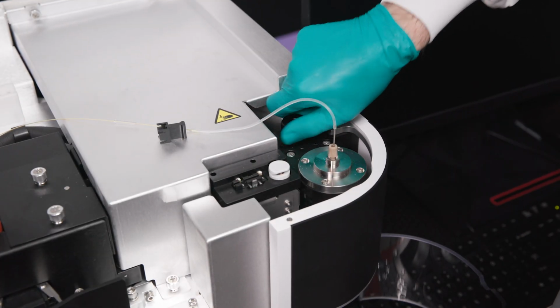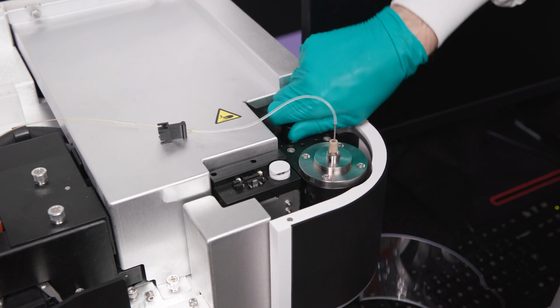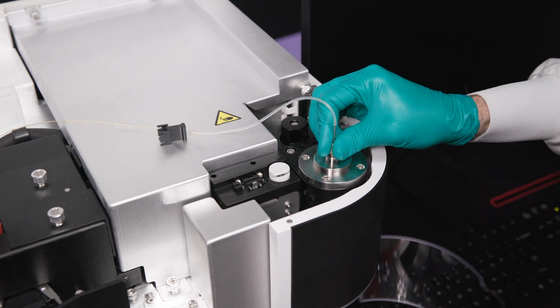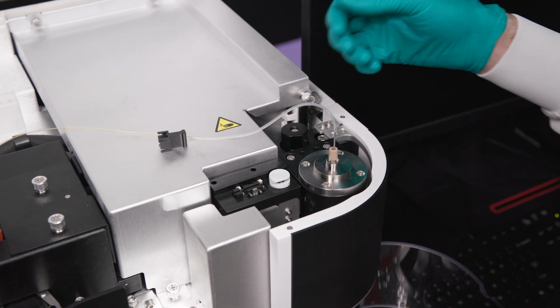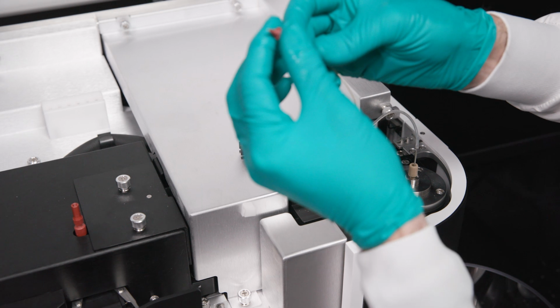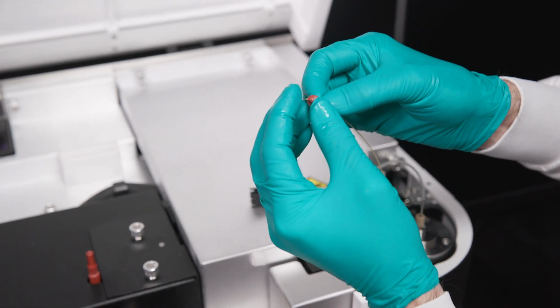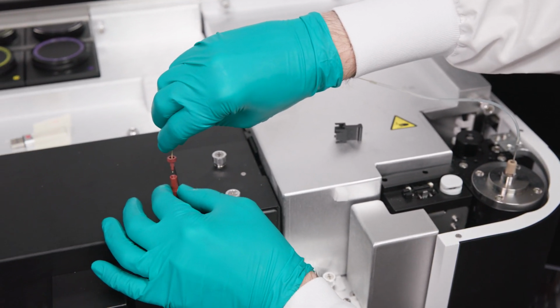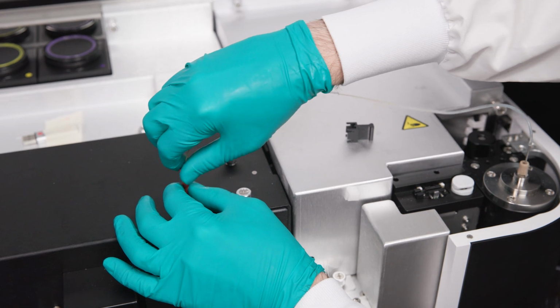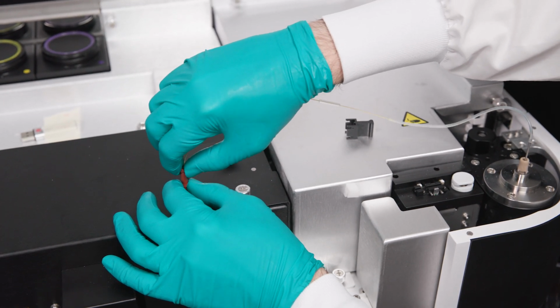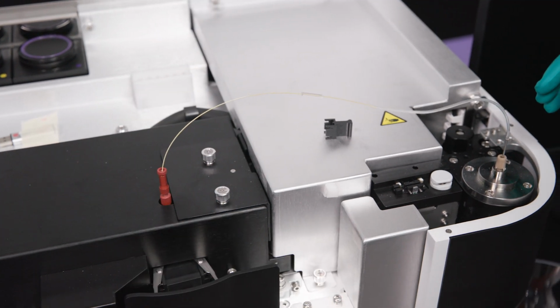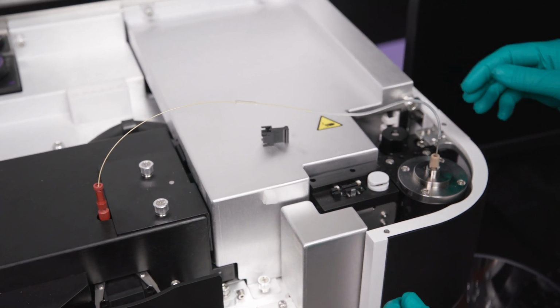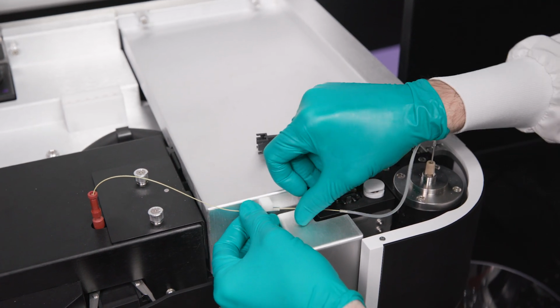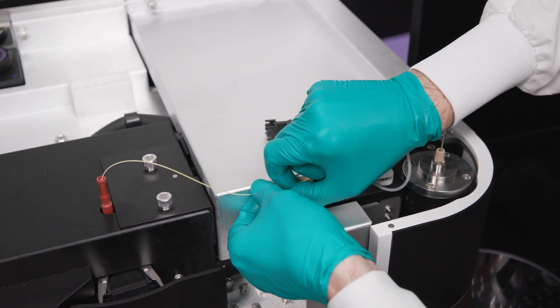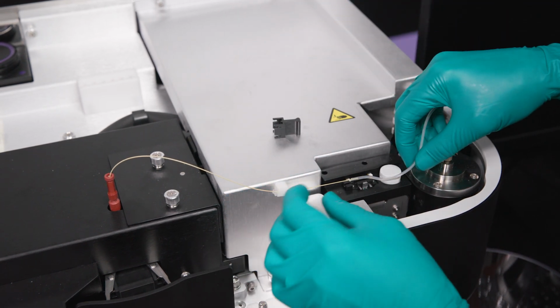And now once we've returned the sample chamber to its upper limit, I'm just going to verify that that's a nice tight fit. I'm also going to confirm that this ferrule is attached nice and tightly to the tubing. And holding this portion so that it doesn't turn, I'm going to finger tighten the other end of the sample line. Place that tubing back in its run.